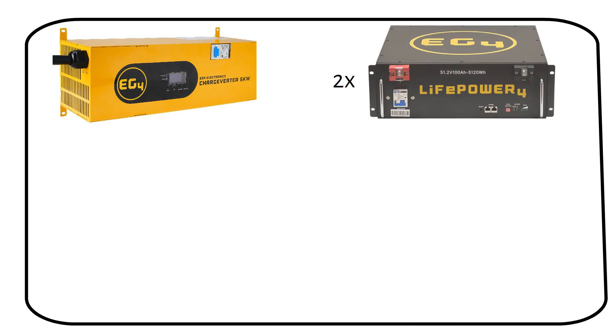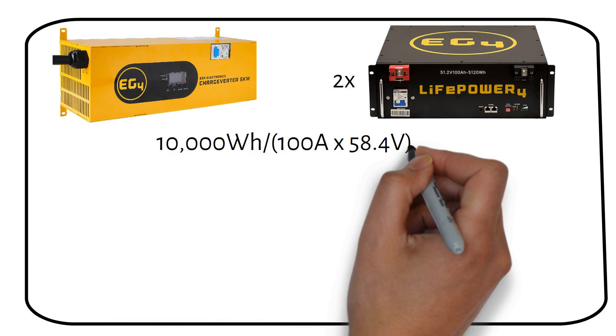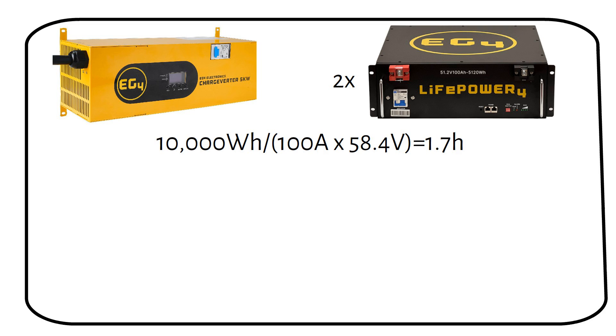The EG4 ChargeVerter is recommended due to its manual current adjustment capability, allowing for precise control over the charging process. If we have two 5 kilowatt hour server racks, it will take 1.7 hours, or 1 hour and 42 minutes, to charge from 0 to 100 percent.